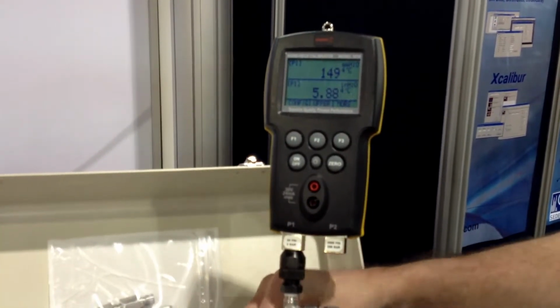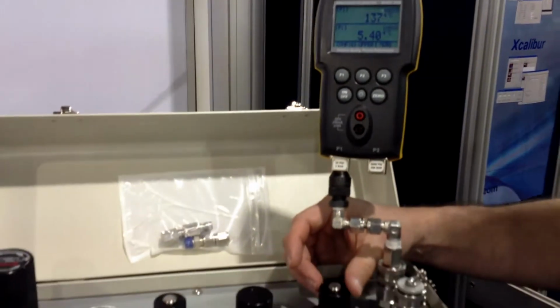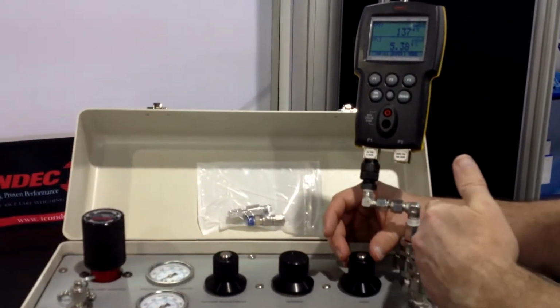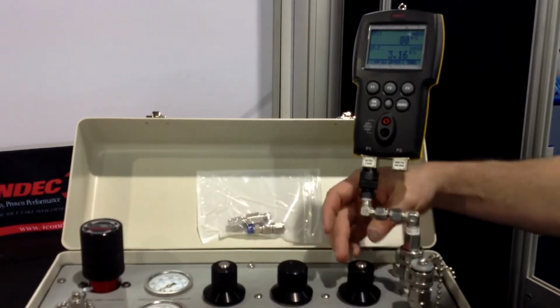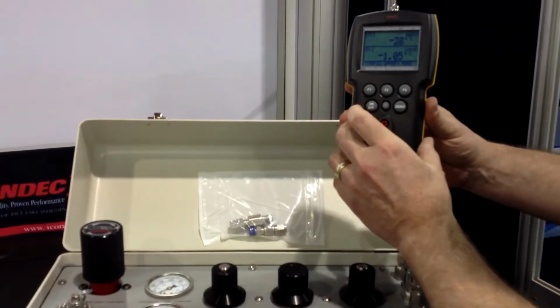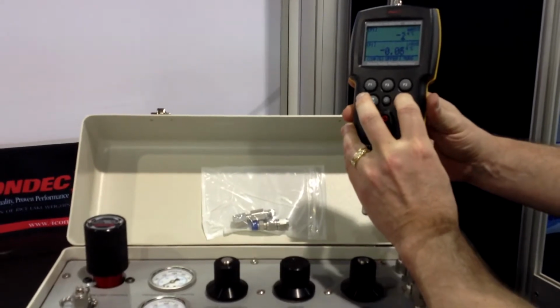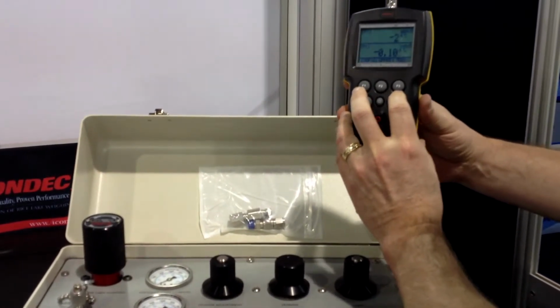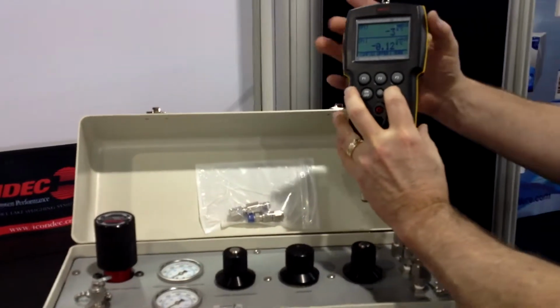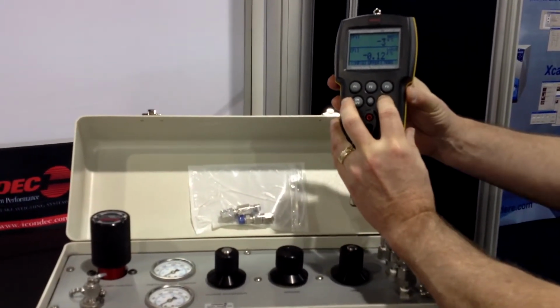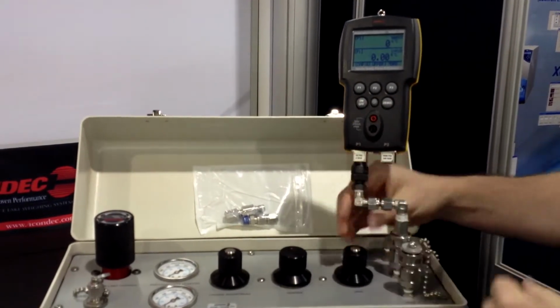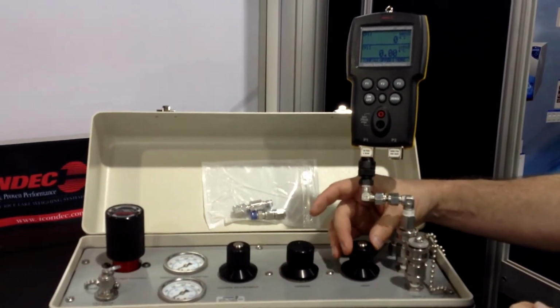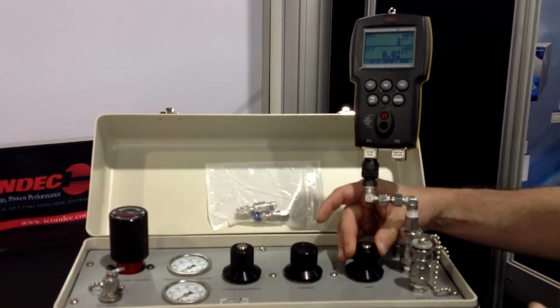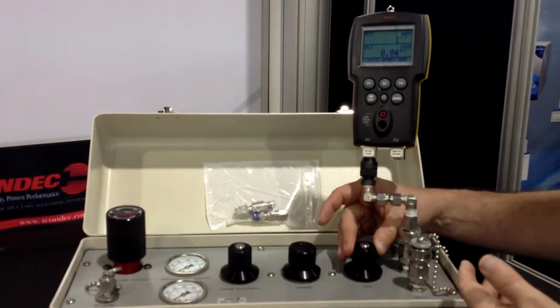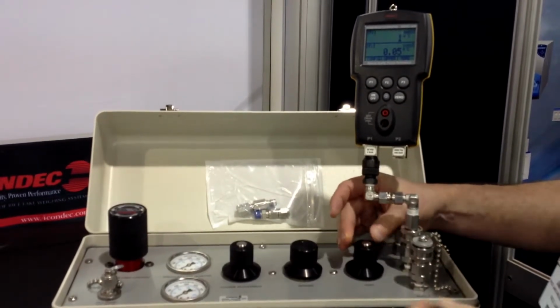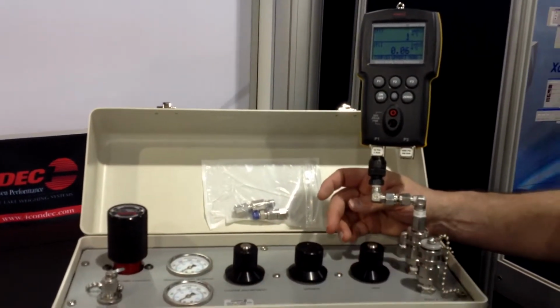What we would do is open up our vent valve, and we don't have this connected to a device under test, so we have to look at it as if it is. We'd open up our vent valve and zero out our unit. This is reading in inches of water, and it hasn't had the proper warm-up at this point either, but we're going to zero it out. Then we would close our vent valve. Now this is used as a closed system. It's not used for flow, so everything has to be set up so that there are no leaks in the system.